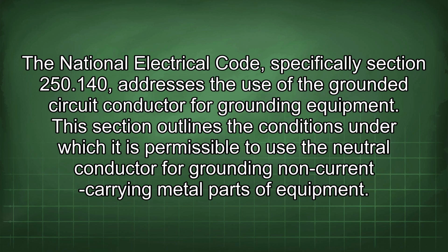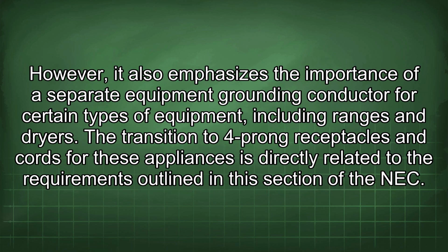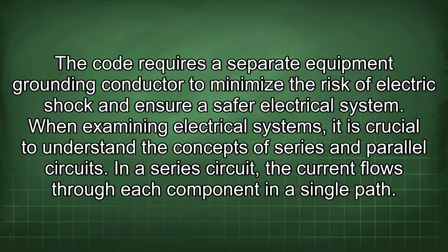The National Electrical Code, specifically Section 250.140, addresses the use of the grounded circuit conductor for grounding equipment. This section outlines the conditions under which it is permissible to use the neutral conductor for grounding non-current carrying metal parts of equipment. However, it also emphasizes the importance of a separate equipment grounding conductor for certain types of equipment, including ranges and dryers. The transition to four-prong receptacles and cords for these appliances is directly related to the requirements outlined in this section of the NEC. The code requires a separate equipment grounding conductor to minimize the risk of electric shock and ensure a safer electrical system.